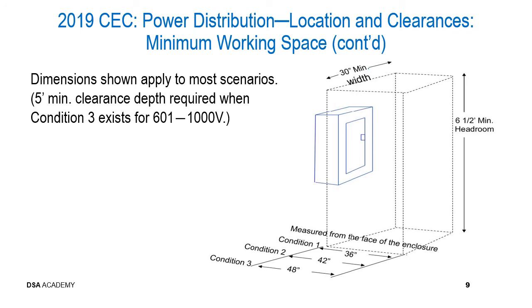Now this would cover most of the scenarios that we see. There is a possibility that a 5-foot minimum clearance depth is required when condition 3 exists for voltage ranges between 601 and 1000 volts.